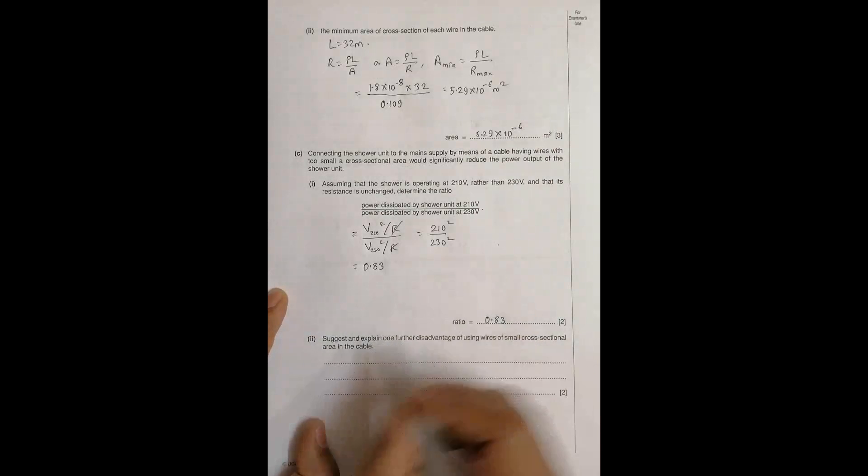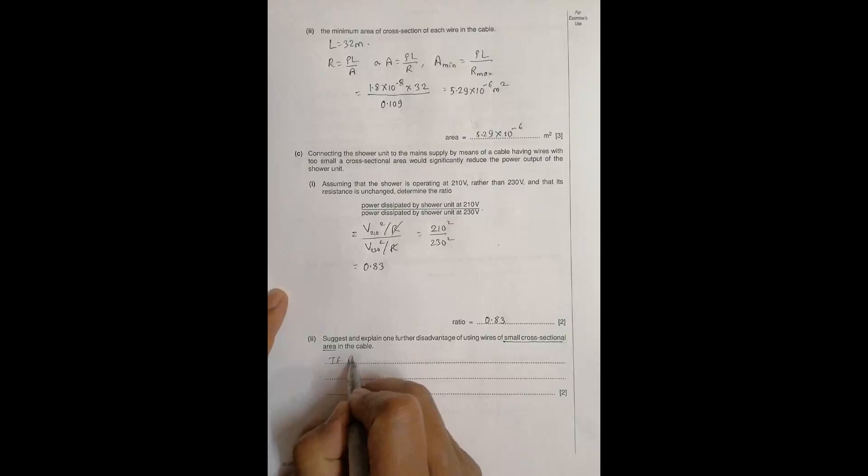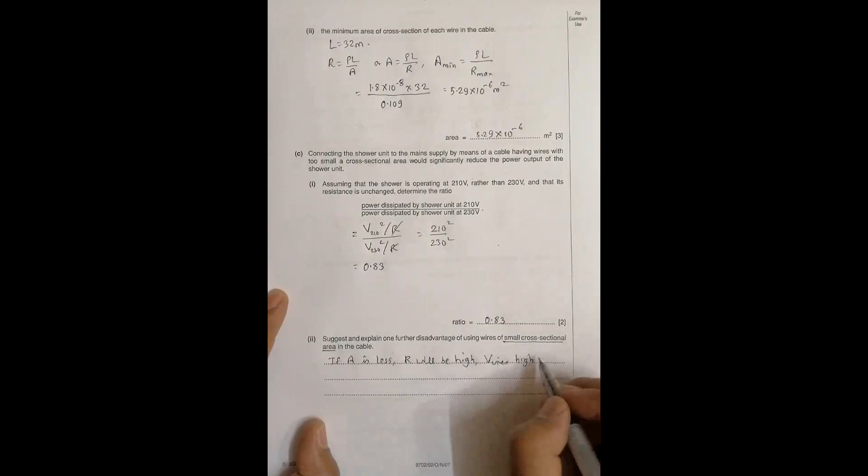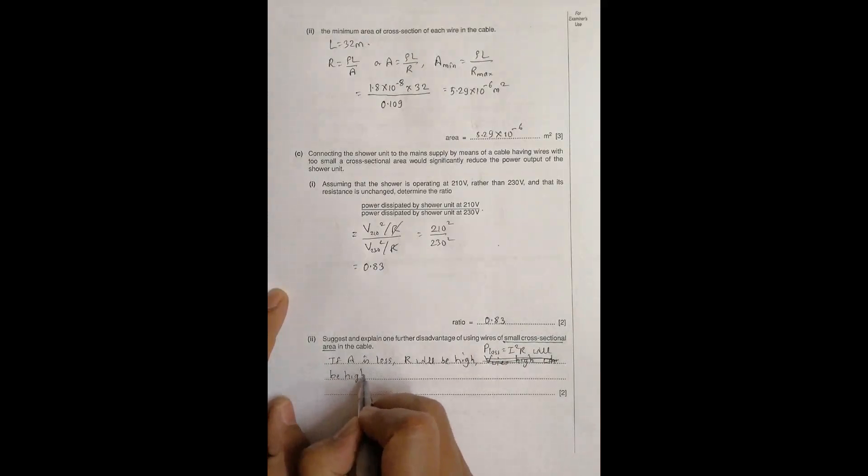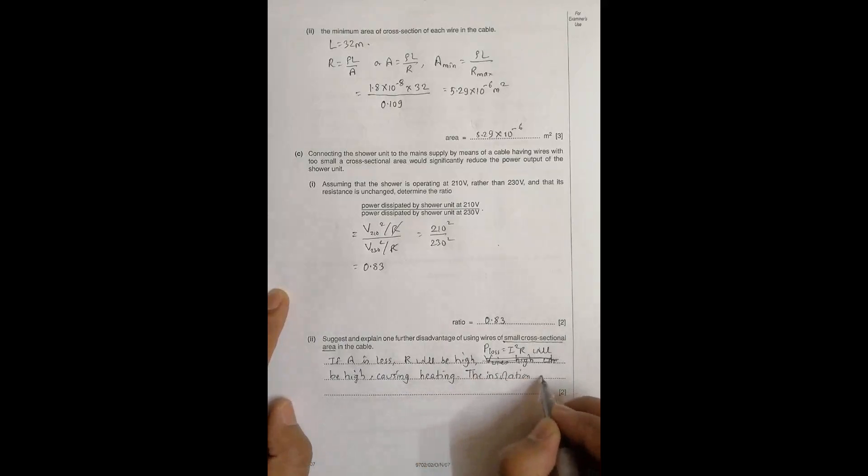Because if we have got small cross sectional area, if A is less, R will be high. So the PD across the wires will be high, or I can say simply if R is high, the power loss equal to I squared into R will be high. This causes heating, causing heating, and because of this heating the insulation might break down, insulation melts, even the wire can melt.